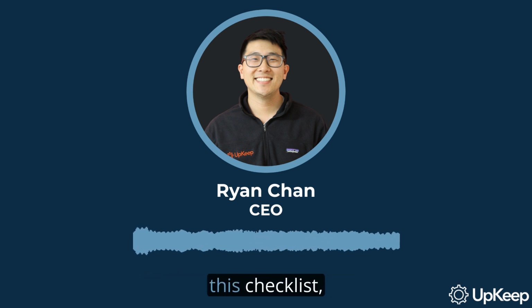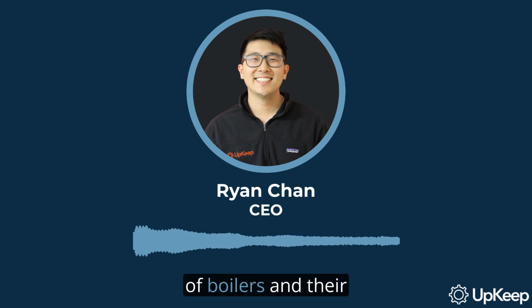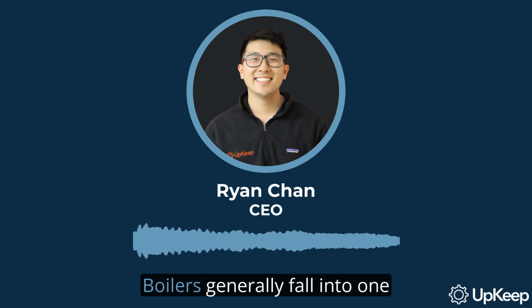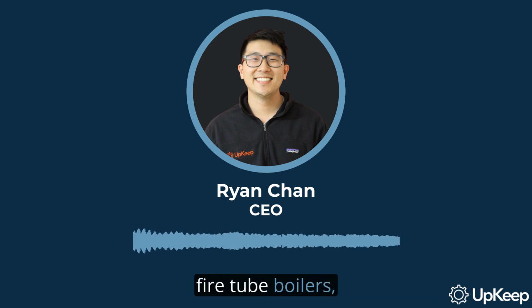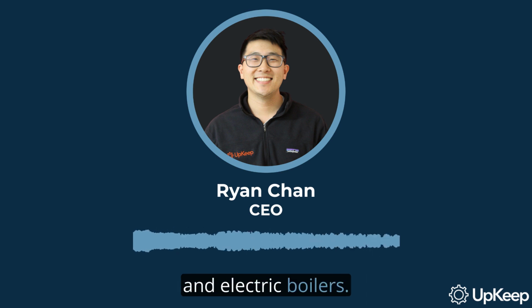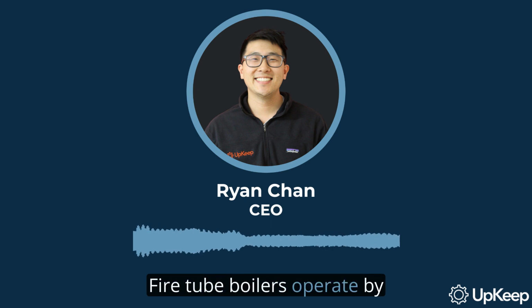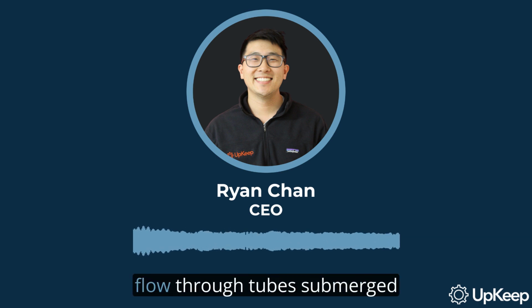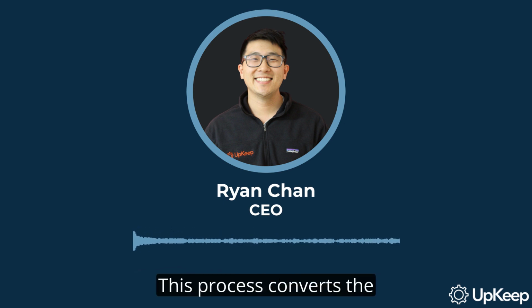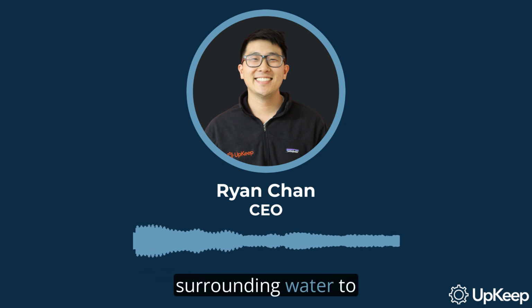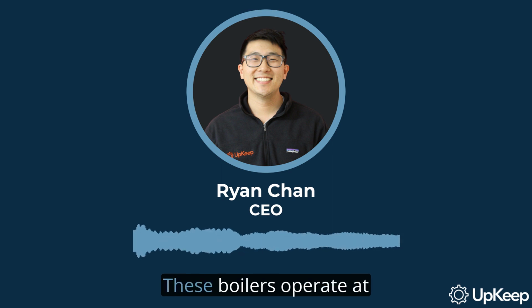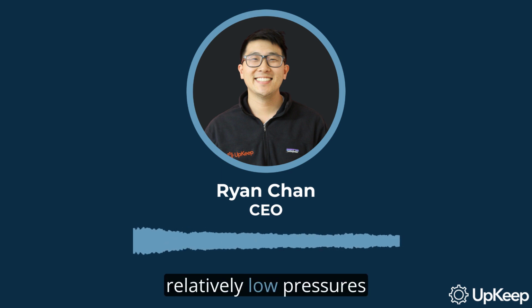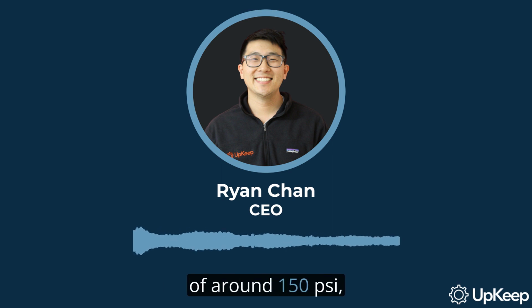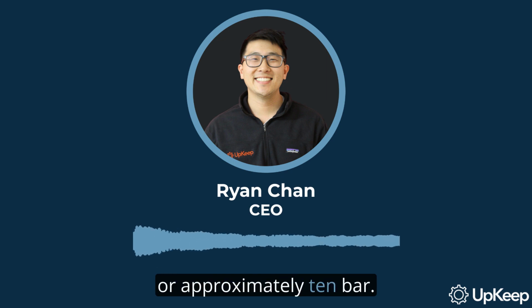To make the most of this checklist, let's first familiarize ourselves with the general types of boilers and their key components. Boilers generally fall into one of three main categories: fire tube boilers, water tube boilers, and electric boilers. Fire tube boilers operate by letting hot combustion gases flow through tubes submerged in water. This process converts the surrounding water to hot water or steam. These boilers operate at relatively low pressures of around 150 psi, or approximately 10 bar.